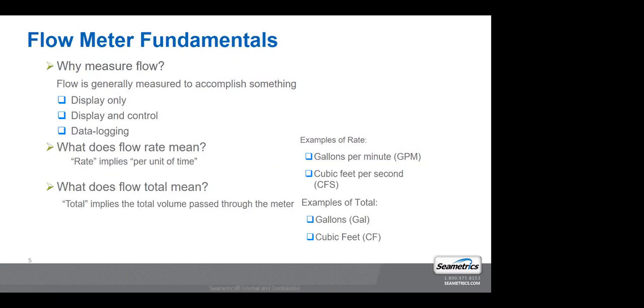If you go to order a meter, that's what the dealer or the manufacturer is going to ask you. How do you want it to read? That's typically what they're asking you. Some meters are programmed at the factory level, and you can't change them in the field once you've purchased them. So if you order them totalizing in gallons, indicating in gallons per minute, that's what you get. You can't change it. Other meters, you can reprogram them in the field. You can't reset the total volume, but you can reprogram the units of measure.